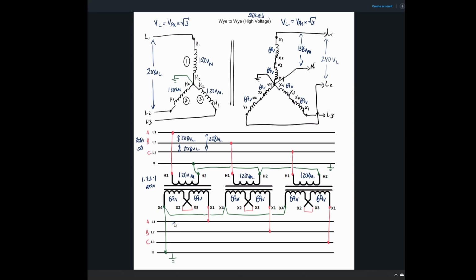So our output voltages, we'll add that to our diagram here. Our line voltage, we just found to be 240 volts from line to line. So we've got 240 volts, 3-phase coming out. And we found that the line to neutral voltage was 138 volts. Again, would you ever see 138 volts out in the field? No. We're just seeing those voltages simply because we only have one voltage to work with in the shop. So output here would be 138 from line to neutral, and we'd have 240 volts from any line to line value.